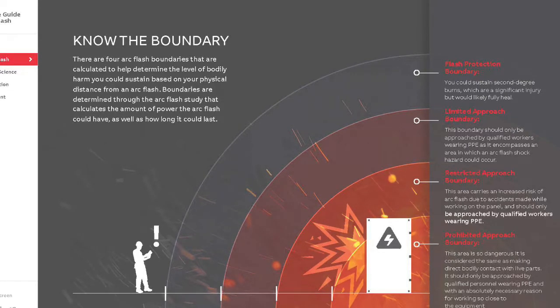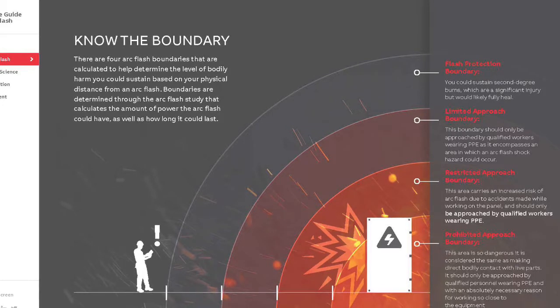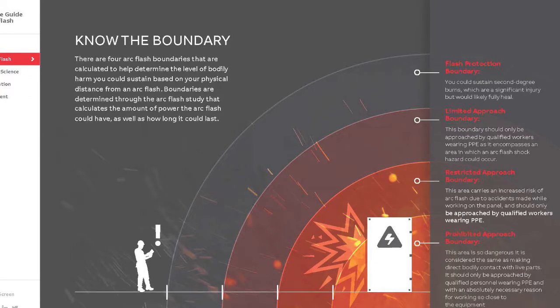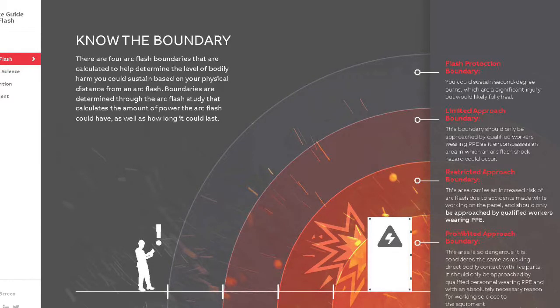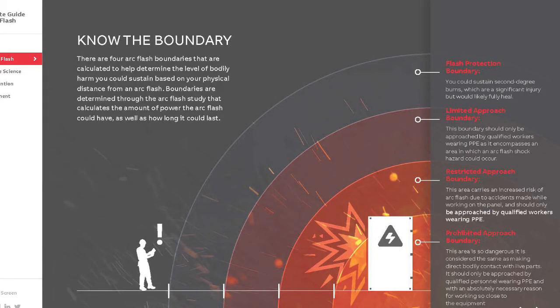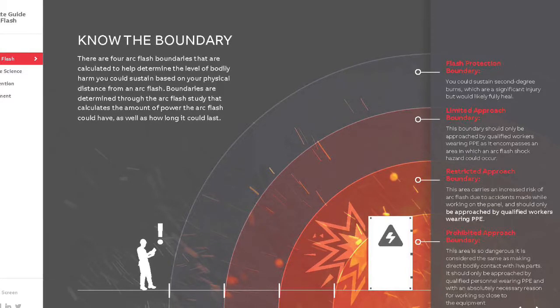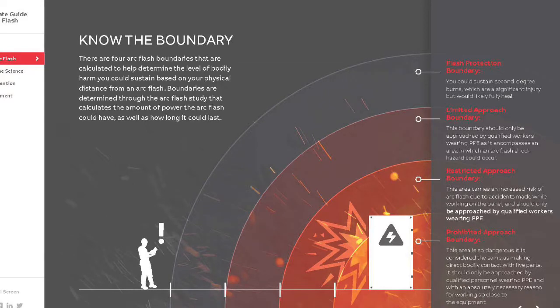The arc flash boundary is the first boundary. It separates an area in which a person is likely exposed to a second-degree burn injury from an area in which the potential for injury does not likely include a second-degree burn. Arc flash burns may still occur outside the arc flash boundary, but they should not be second-degree or worse. The onset of a second-degree burn on unprotected skin is likely to occur at an exposure of 1.2 calories per square centimeter for one second. Calories per square centimeter is also known as cal.